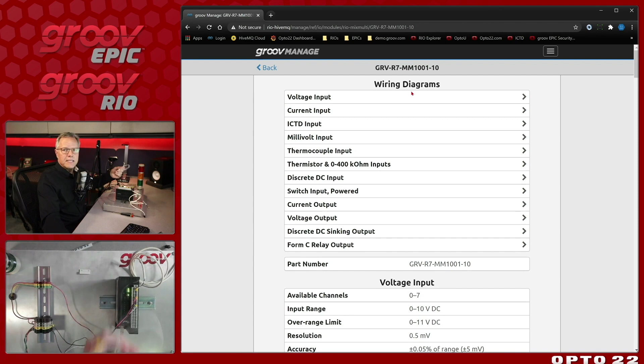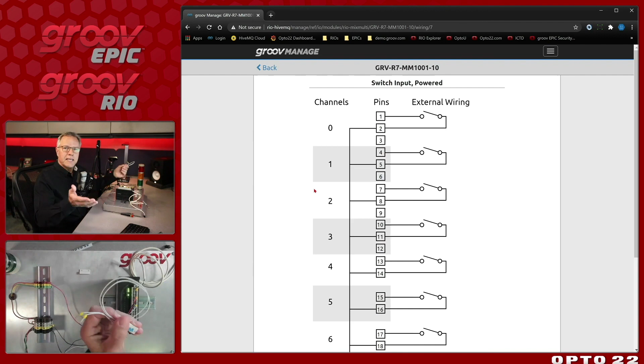This little device I described is a dry contact, and in that case it needs to be powered. So I can come right down here to switch input powered, click on it, and look at that. My wiring diagrams for all my channels of I/O are built into the system. Channel 0 was actually the temperature sensor, so I'm going to use channel 1, and it says to use pins 4 and 5.